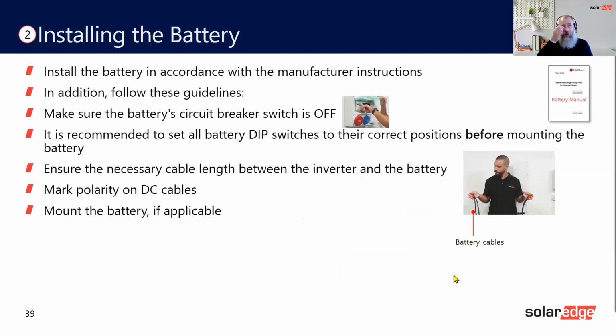So installing the batteries, obviously make sure everything is turned off, read the manual that comes with it, read the quick guide, read the manual as well. It's very important you do that. Then make sure that you set the battery dip switches before mounting the battery, and I'll show you where these are. Make sure the cables are the right length, so no more than 5 meters for the DC to the battery, and mark the polarity. So mark both ends of your positive cable. Unlike the PV array, which is in series, so plus to minus, the battery connections are always plus to plus.